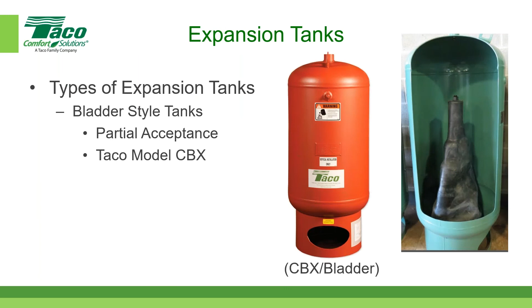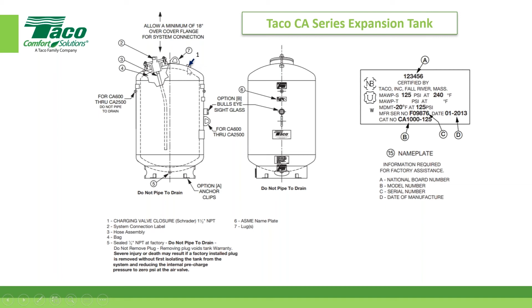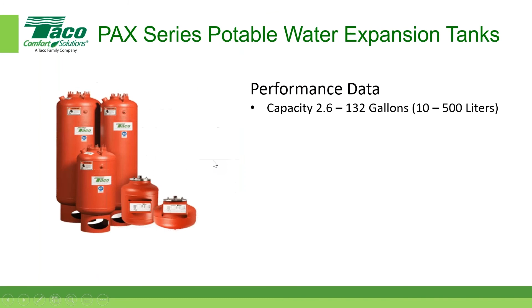If your bladder fails, the water will fill the cavity around the bladder, and over time the air in the tank goes into solution and the tank becomes waterlogged. That's usually when people notice, because the safety relief valve goes off since the water has no place left to expand. The easiest way to check is at the charging valve, labeled number 1 - it's a Schrader valve just like on a car tire. Press it in, and if water comes out, the bladder has failed. That's the simplest way in the world to check it.